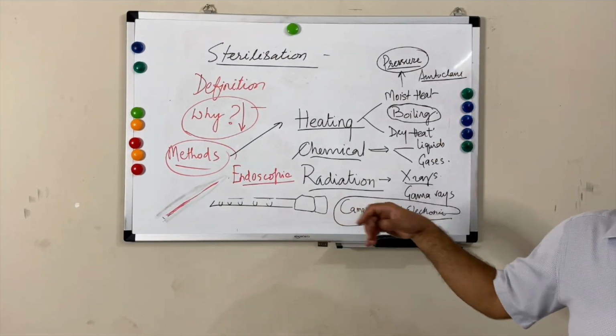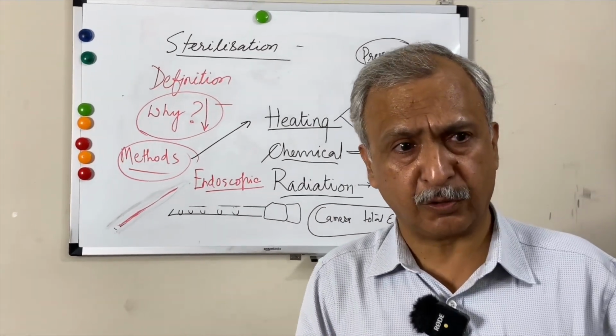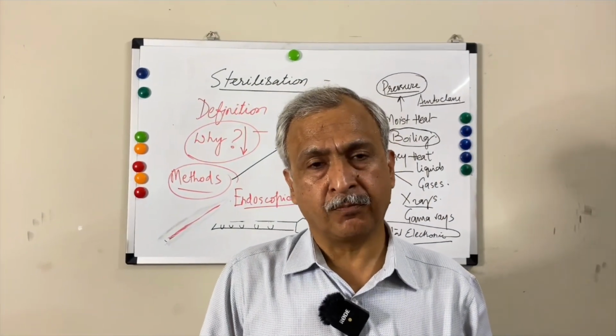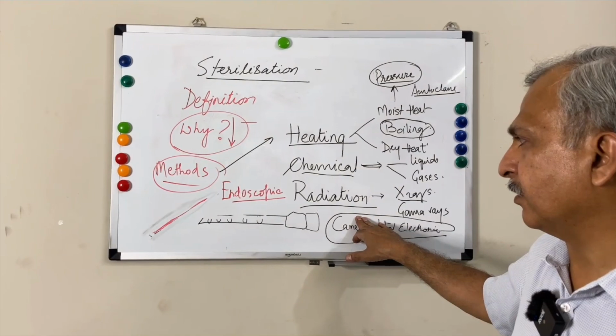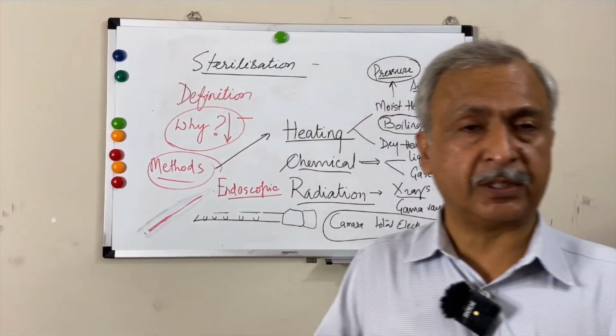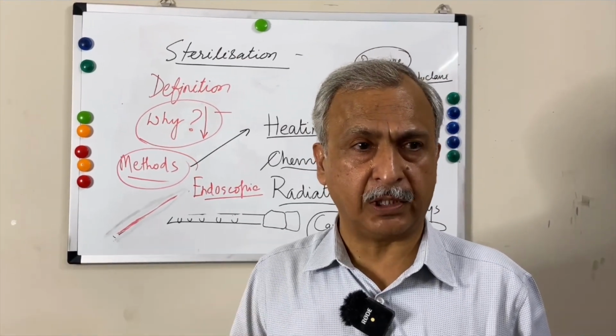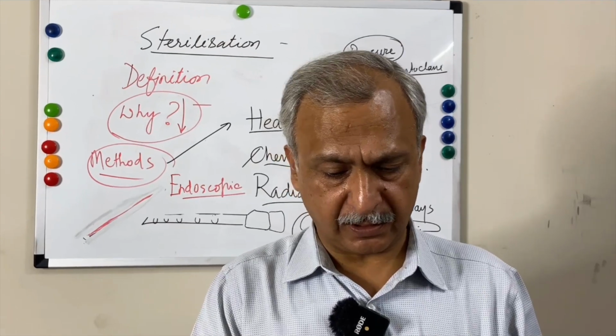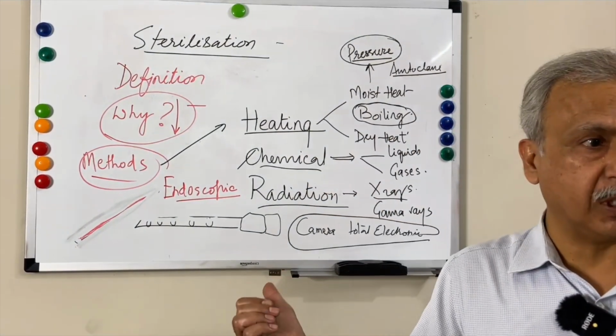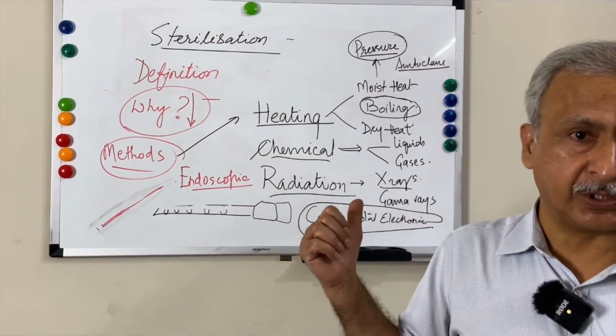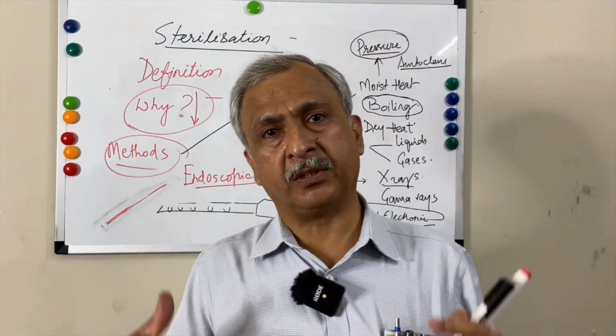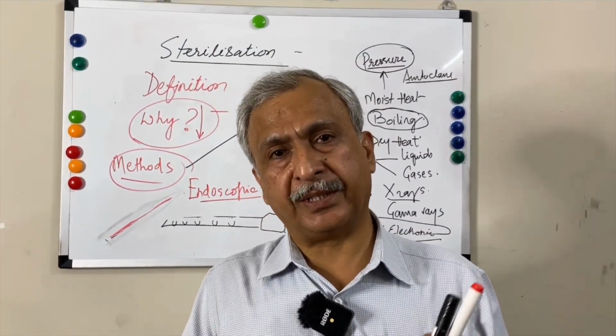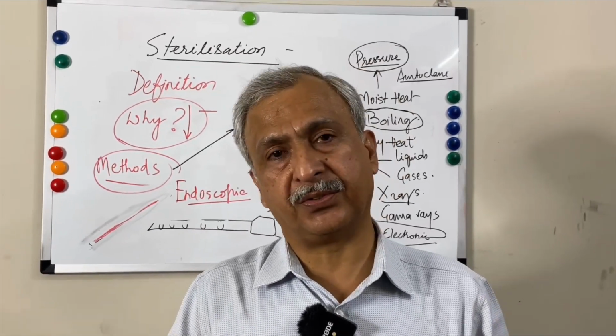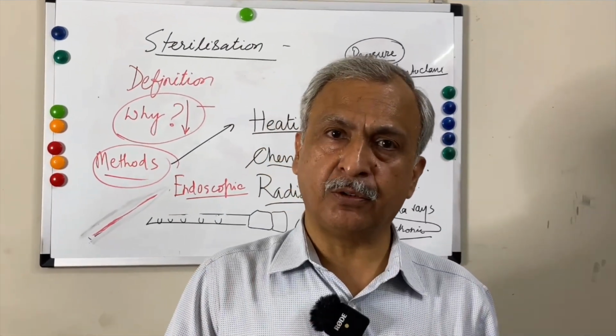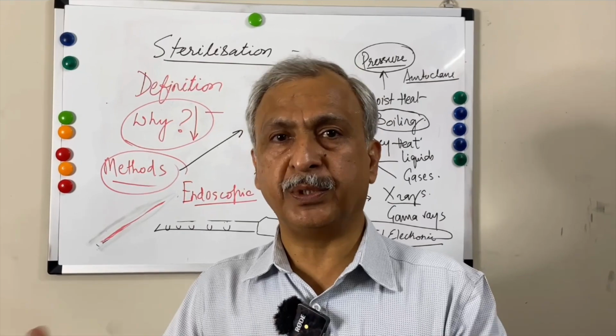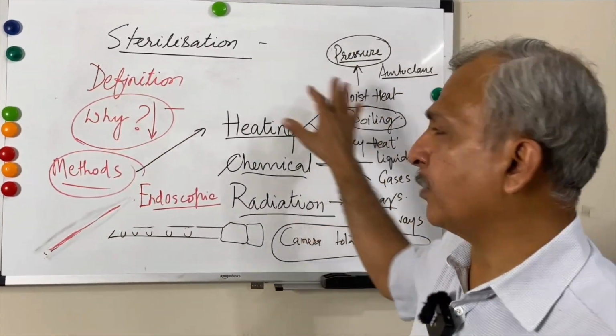Next comes the camera. Camera contains the electronic equipment. As you know, these electronic equipments are very sensitive to heat and moisture. So if these are not meant for tolerating the temperature and the pressure, if you put that camera into the autoclave, so ultimately when you bring back the camera out of autoclave, that camera will be totally destroyed and cannot be used for the surgical procedure. So we have to be very specific कि कौन सा इंस्ट्रूमेंट हमारे पास है, उसकी क्या स्ट्रेंथ है, उसकी क्या वीकनेस है, उसको हमने किस तरह से स्टेरिलाइजेशन करना है, so that the instrument also does not get damaged, proper sterilization also happens and we can use it also. So these are the common basic things about the sterilization.